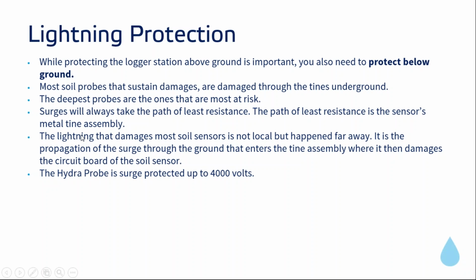So we offer a strategy for grounding the area around the soil sensor, so that the surge will take the path of least resistance and get shunted to ground, and not get into the probe and damage it. And so the HydraProbe is surge protected up to 4,000 volts, which it can survive. But of course, some of these surges are much higher than that we see.